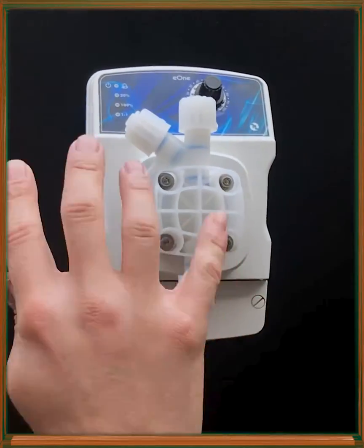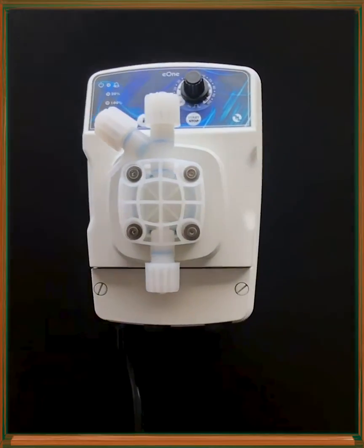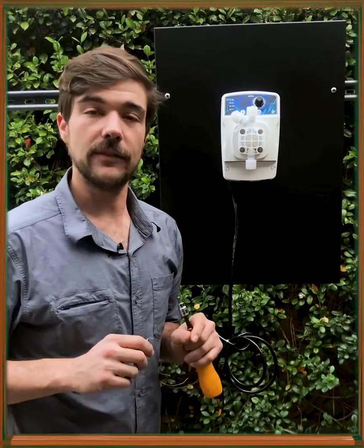You want to make sure not to over tighten these screws because that can flatten the pump head seal or cause a vapor lock, which will both affect the functionality of this pump.